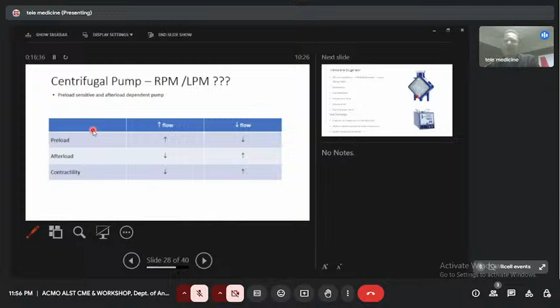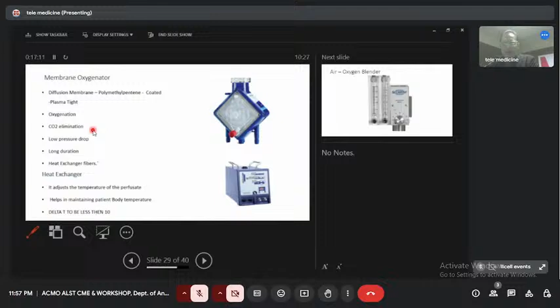So coming to the membrane oxygenator, it has the heat exchanger fibers in it, like your lungs, a pathway for the air, oxygen, a pathway for the blood, can exchange the gases, and a similar heat exchanger that you have in the machine, it heats up the RO water only, but you have to be specific that the temperature difference between this machine and the body should not be more than 10 degrees. Okay, that is the limit to avoid any hemolysis or trauma to the blood.